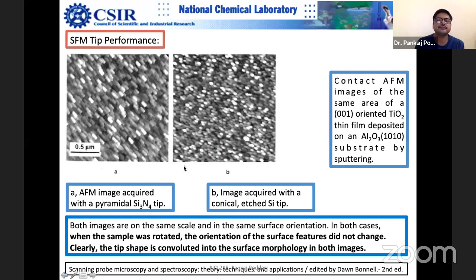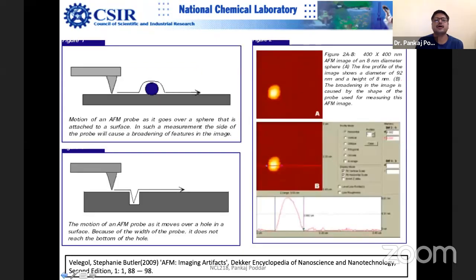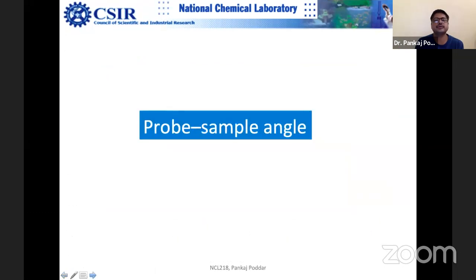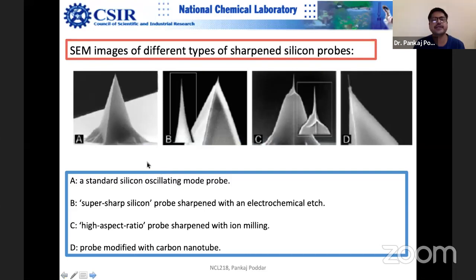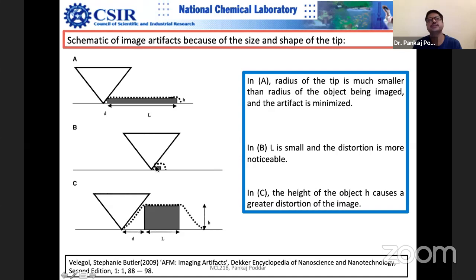In the case of spherical-shaped samples, we cannot exactly image them as spherical. But if we know beforehand it is spherical and we know the tip radius of curvature — say around 10 nm — and the particle is around 20 nm, then there is no problem. There are specialized super-sharp probes available, and you can also etch them in the dual-beam FIB-SEM. It depends upon cost — cheaper probes are designed just to give some idea about roughness.